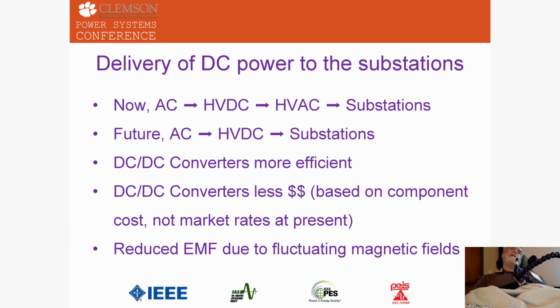It's true to say that DC-DC converters, if you look at the component cost, should be about 30% less expensive than an equivalent kilowatt capacity DC-AC converter. Now, that's not true of market price because there's not a sufficient market in this voltage range. I'm proposing sort of a replacement for that intermediate voltage stage.